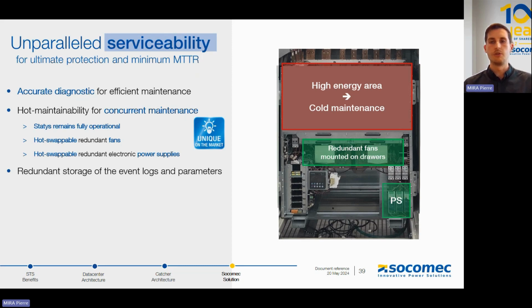On top of that, the customer can purchase a spare module in order to have a factory tested module and bring it live in less than 30 minutes through the cold swap patented advantage. So it's another level of maintainability, having hot swap features and cold swap features. It's a very advanced design in order to increase the maintainability of the data center architecture.